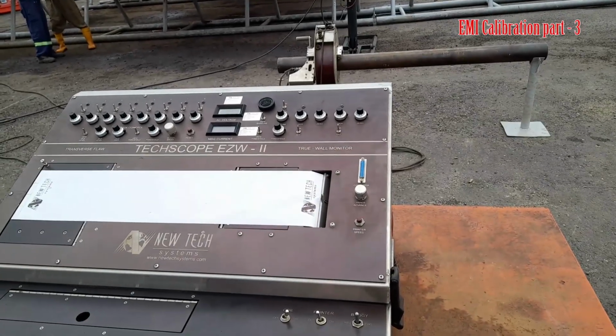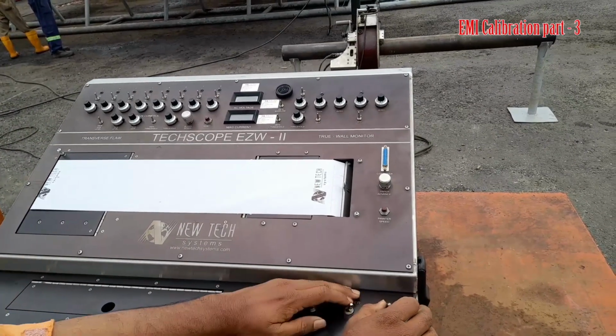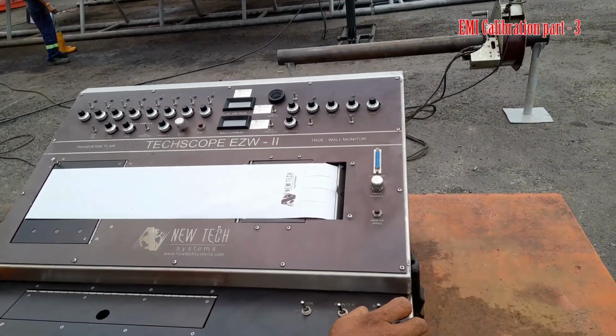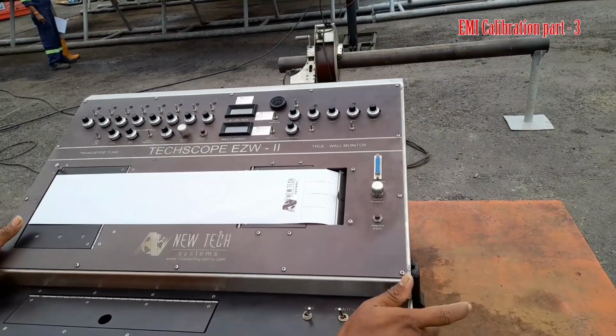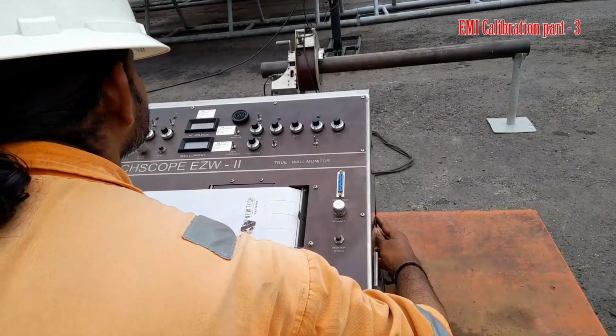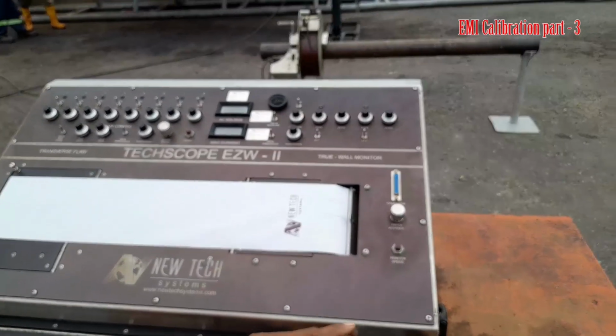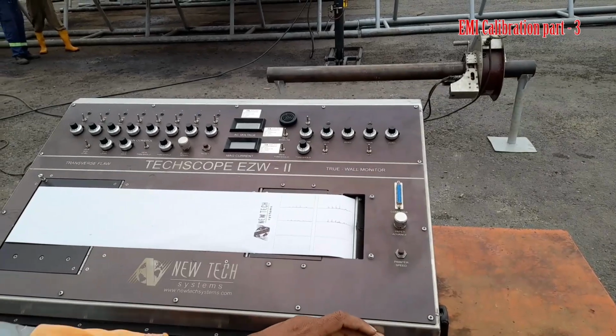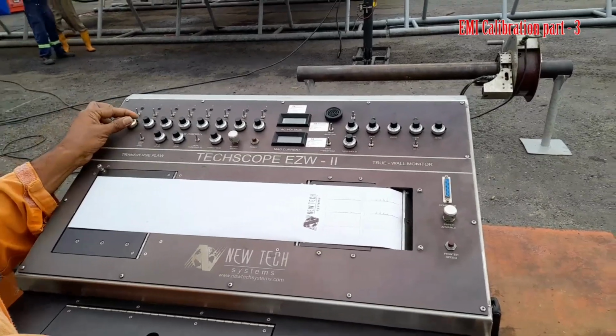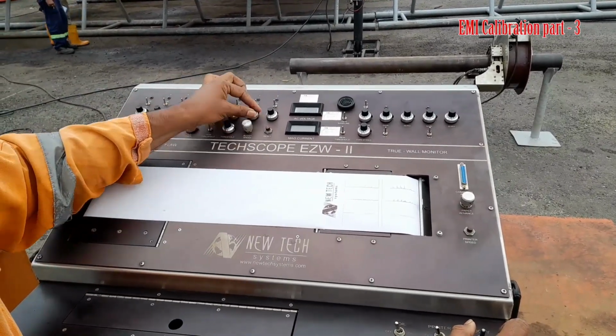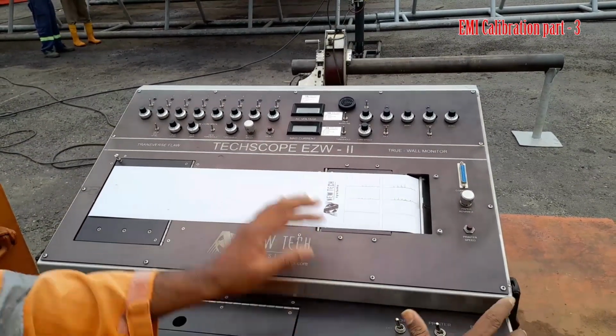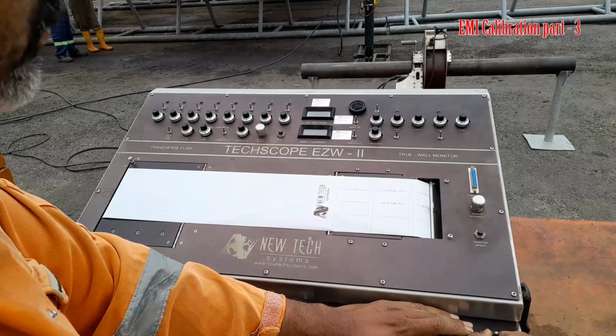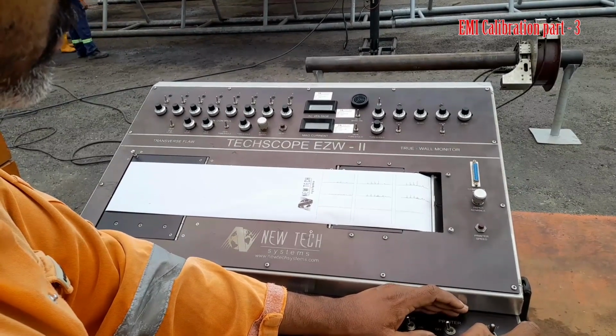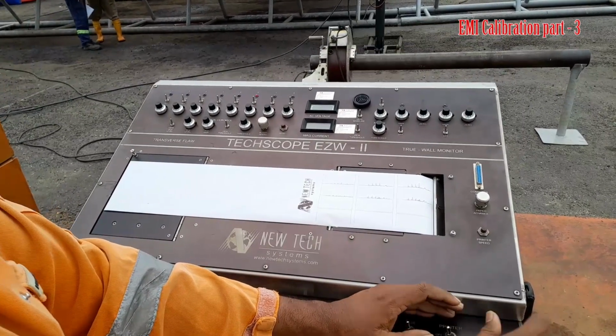So the next step: if right now you get the single kick at 5 mm, you have to increase some value, blindly increase some value, then run the buggy head in reverse and place it at the first position. Again check the alignment of the shoe, then run again. Then you get 12 mm. You assumed your kick point at 10 mm, but it was 12 mm. So run in reverse again. Adjust a little bit, reduce the gain, which means rotate the control anti-clockwise. Then it will reduce. Achieve 10 mm. Again run it. It is at 10 mm. It's okay. Repeat this setup for all 8 shoes.